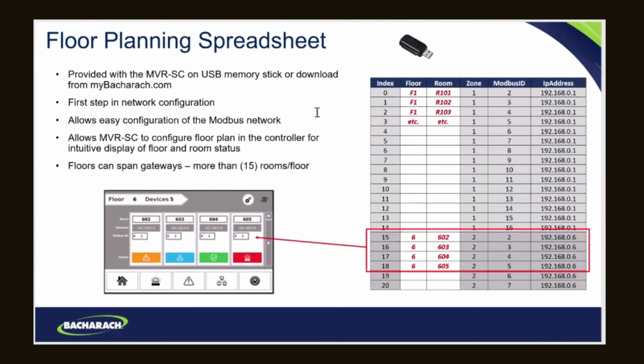This is the floor planning spreadsheet. There is an SD card or a USB stick or some sort of a device that has this CSV file on it. And what you're going to do is go through and fill out the floor and the room information. So all of the things in gray are already configured. And you'll see that you can get up to 15 gas detectors on each one of these gateways.